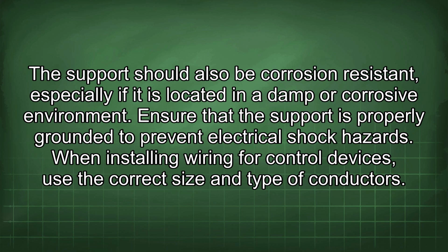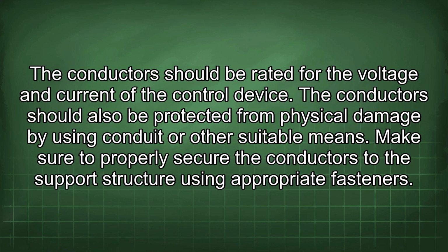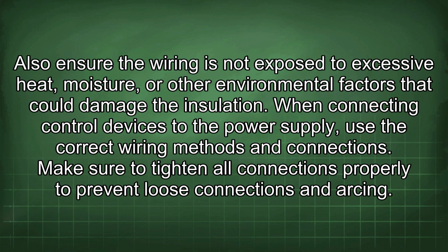When installing wiring for control devices, use the correct size and type of conductors. The conductors should be rated for the voltage and current of the control device. The conductors should also be protected from physical damage by using conduit or other suitable means. Make sure to properly secure the conductors to the support structure using appropriate fasteners. Also ensure the wiring is not exposed to excessive heat, moisture, or other environmental factors that could damage the insulation.